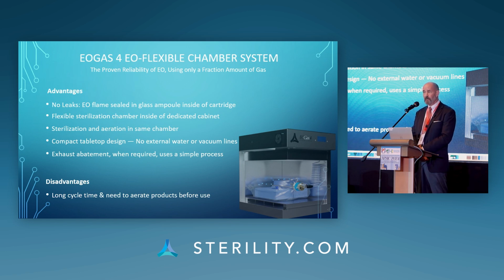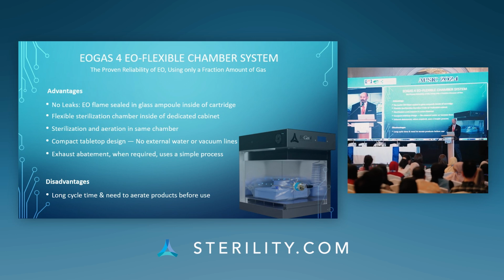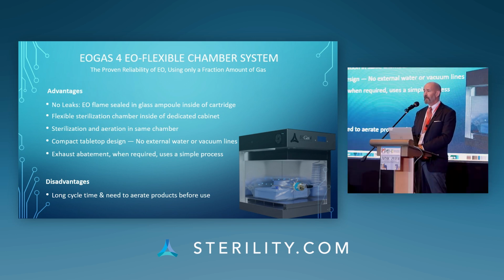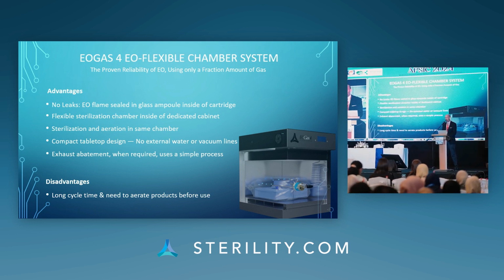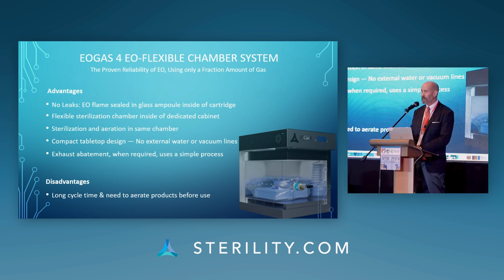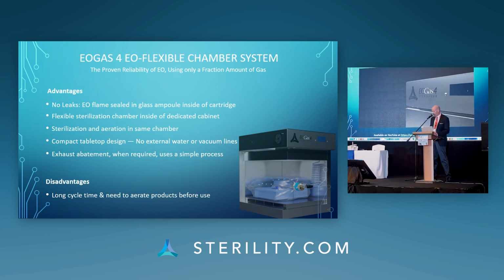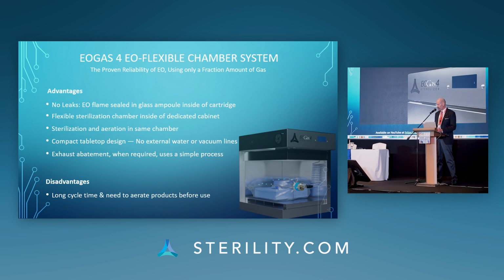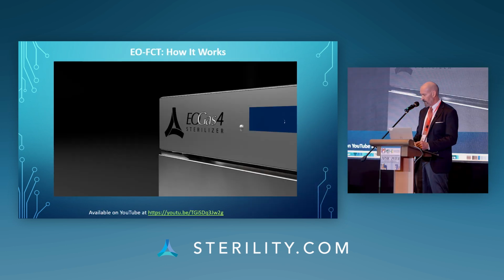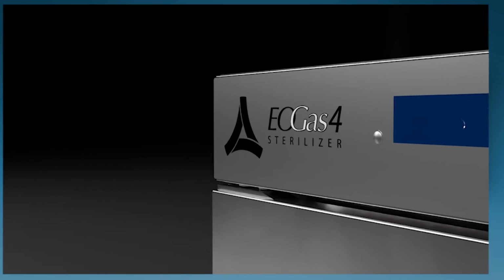The disadvantage, and as I said, all systems have pros and cons, the disadvantage is still a relatively long cycle time. This is going to be an overnight cycle. Sterilization is going to take 6 hours. Aeration is going to be 6 hours after that for most endoscopes. I have a short video here.